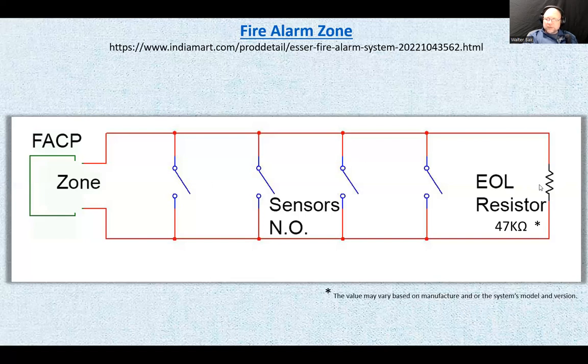The purpose of the end-of-line resistor is to tell the system that when it sees that resistance, the system is at ease and there are no broken lines along the way. That line can be broken, can be interrupted. If you put that end-of-line resistor at the terminal, and if the line is broken, the system is not going to know. So if any sensors are being triggered, it might not be functional, and the system will never know that the line is broken. So it should be at the end of line. It's called end of line resistor. There is a reason why I'm saying that. It's because, never mind.